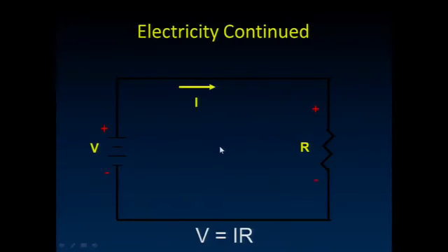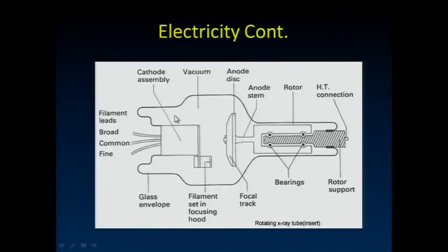And I'll make a point of that as we look at some X-ray tubes and talk about some of the fundamental little circuits that are there. So here's one. And really there are three electrical circuits that are going to be involved here. One is we're going to apply a small voltage across this filament, like in a toaster or like in a light bulb. And when we do that, it's going to heat that filament up, and electrons are going to get boiled off the surface of that. And with nothing else present, they really wouldn't do a whole lot. So we also apply a large voltage between this point on the filament, the negative terminal, or the ground here, and the positive terminal on this anode.